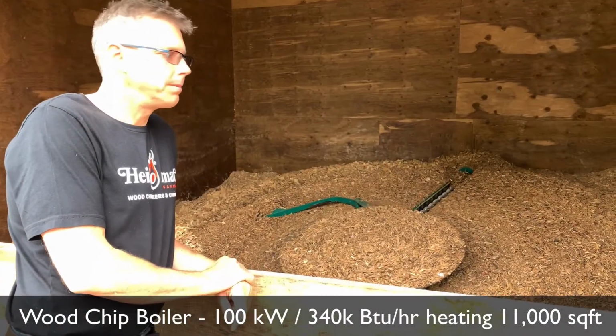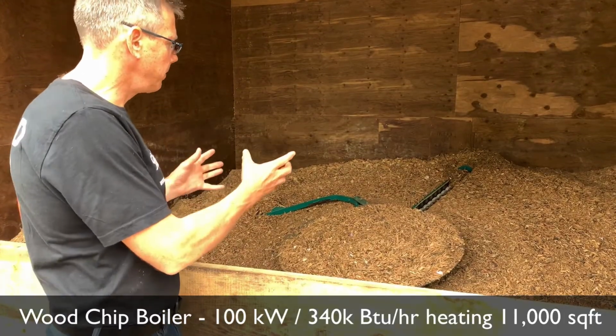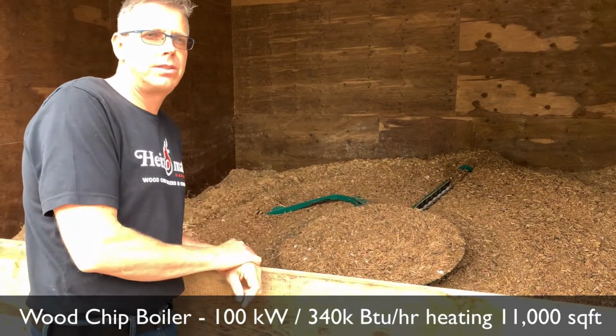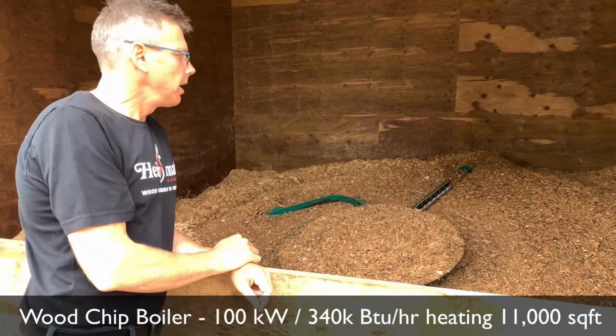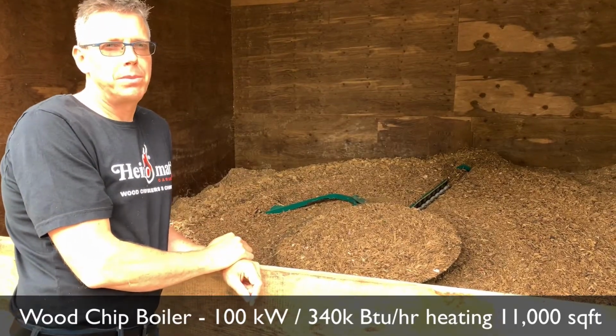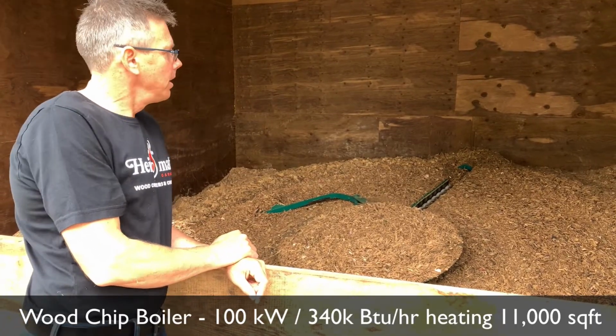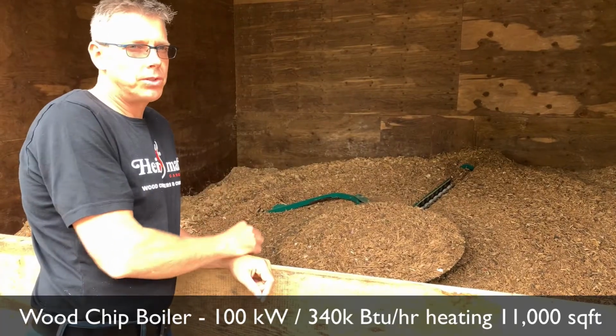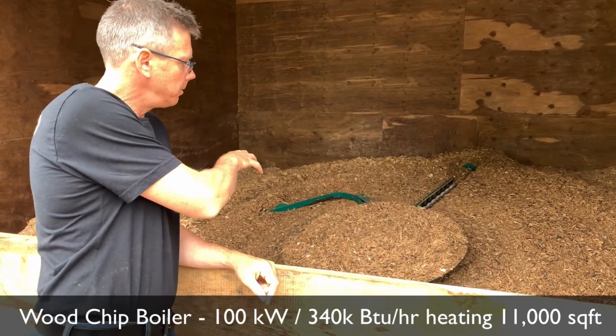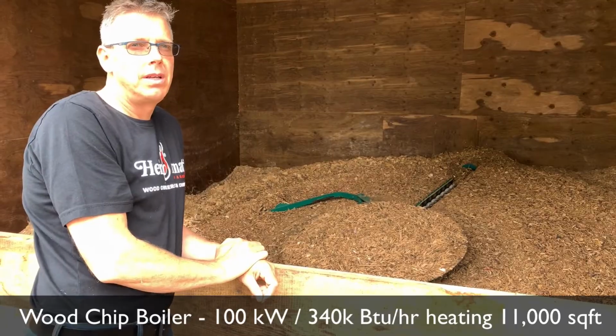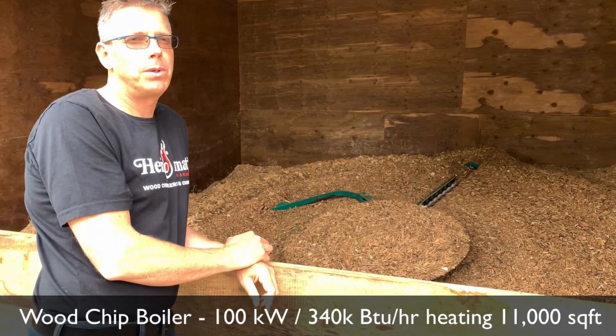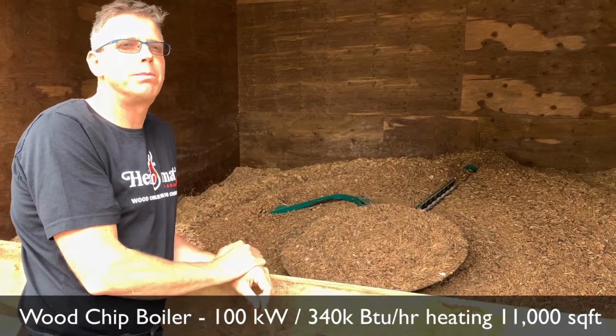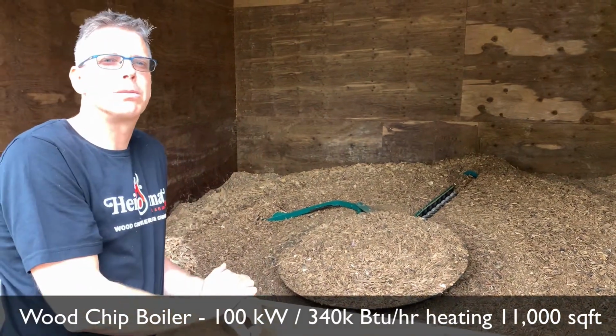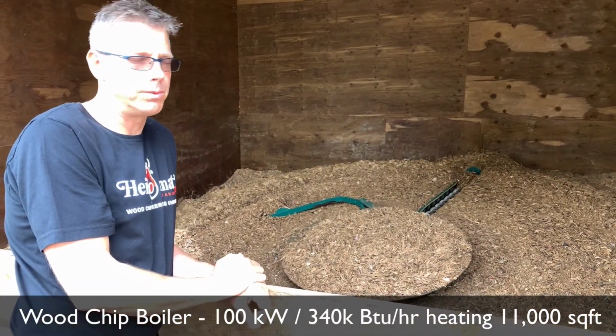The feed system is fairly simple. As the bunker empties, the arms extend out to draw more fuel in — a fairly simple system, but with a lot of refinement. There's a motor inside the boiler room that drives the auger, which drives the gearbox. The gearbox is a very heavy-duty sealed gearbox that should never need any maintenance, so there's actually nothing to maintain within the bunker itself.